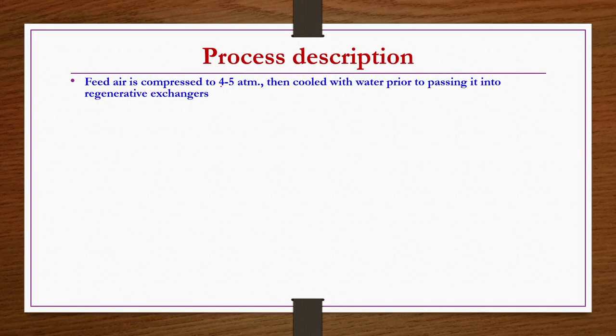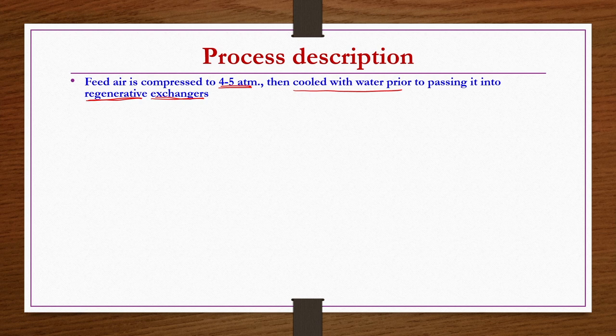Now we see the process description, which we will also see in the flow sheet. The feed air is compressed to 4 to 5 atmospheres. After compressing, it is cooled with water prior to passing it into regenerative exchangers. These regenerative exchangers are very important aspects of the process; up to this exchanger step is where the main difference between one process and another lies.